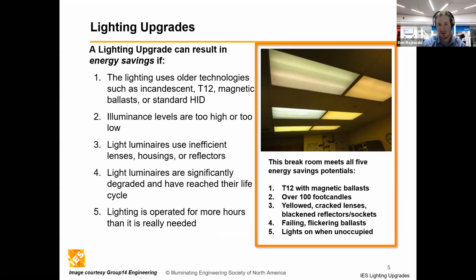The picture on the right shows old T12 fixtures with inefficient ballasts. You've got a lot of light, like 100-foot candles or 1,000 lux in a space that probably needs 300 lux. So you could reduce the number of fixtures, make the fixtures more efficient, add lenses that aren't cracked and broken, and deal with other failing issues to make the space more efficient, better lit, brighter, while still saving a lot of energy.